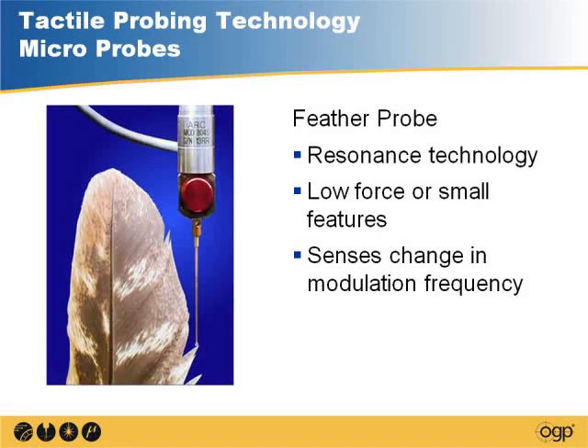Okay, the next sensing technology that we're going to talk about is the same kind of probe, sticking with the tactile theme. This is a more unique probe for measuring either very small parts or flexible parts. The other conventional probes typically require some magnitude of force on the part, and in some cases that just can't happen, or it's undesirable. So this technology uses resonance. This probe is hanging down and it's actually resonating at this optimum frequency. As it approaches a part, that frequency changes and immediately a trigger or a point is detected. It senses that change in modulation, and that's how it triggers that XYZ point.